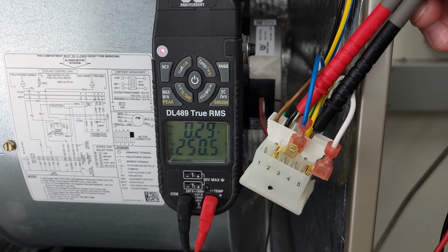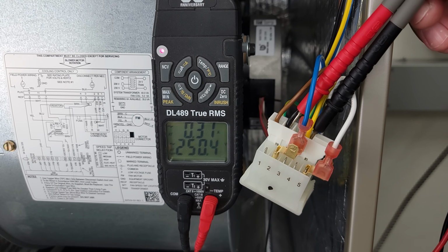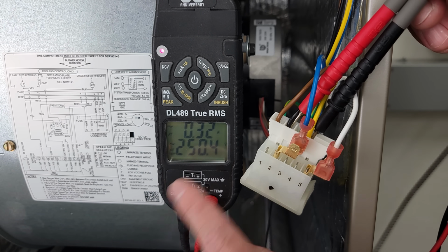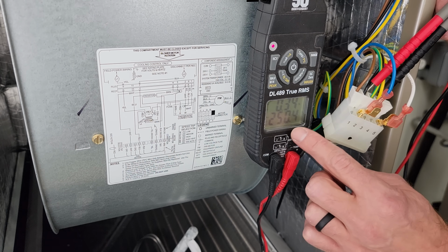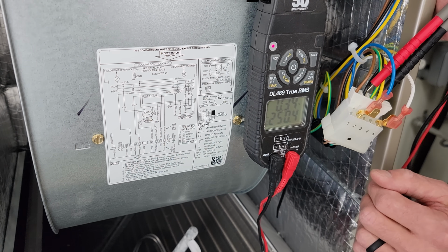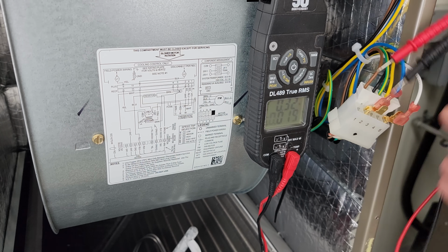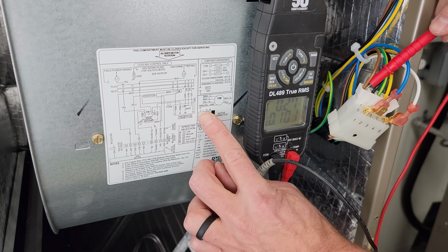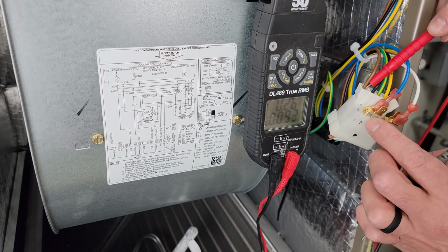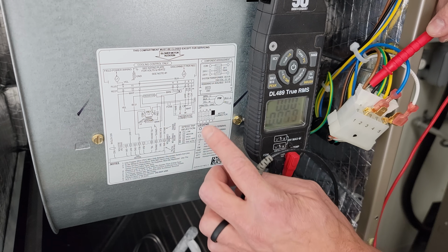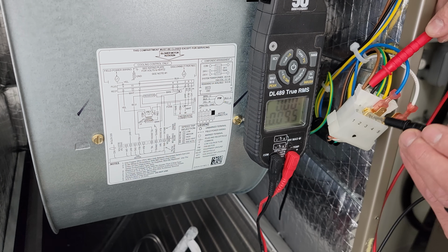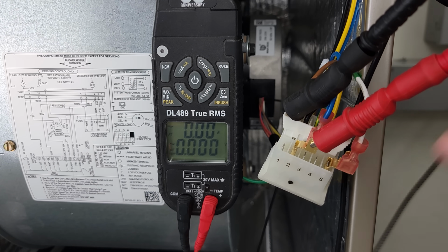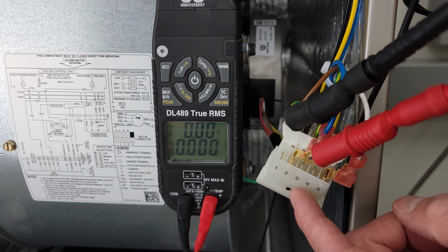So right now the thermostat's not calling for air conditioning or fan or anything to turn on, and this is correct. We have our high voltage power. In fact, actually the building's power is a little high at 250 volts. But now what I want to do is I'm going to stick this one probe in the 24 volt common right here. As you can see on the wiring diagram, it's right there. And we're going to stick our other probe in the number 2 speed connector for our motor speed. I've switched to our alligator clips just to make it a little easier to show.